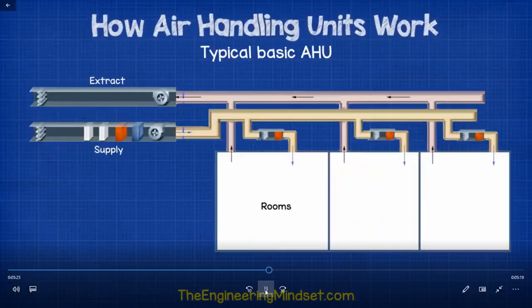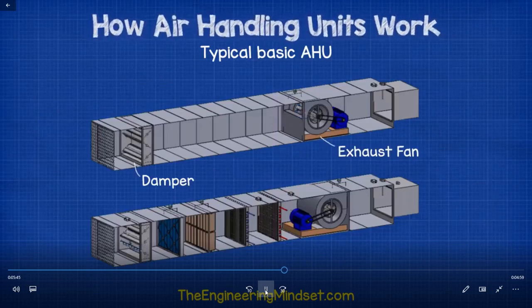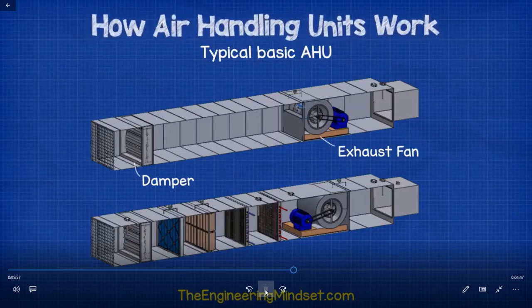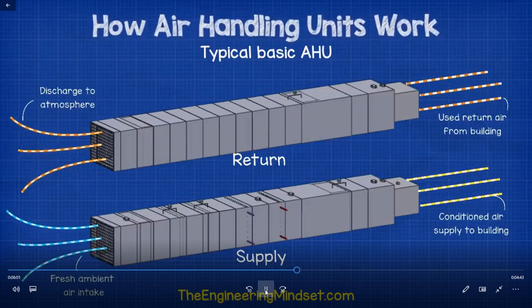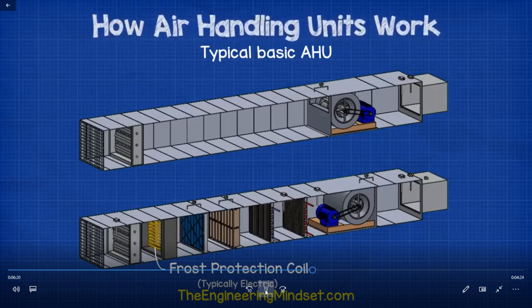The ductwork sends conditioned air around the building to designated areas, and return ductwork brings used air back to a separate part of the AHU. The return AHU in its simplest form has just a fan and a damper — the fan pulls air from around the building and pushes it out of the building to atmosphere, and the damper closes when the AHU turns off. In cold climates where temperatures reach freezing point or close to it, a preheater is found in the fresh air intake — usually an electrical heater that activates around 6°C (42.8°F) to protect the internal components from frost.